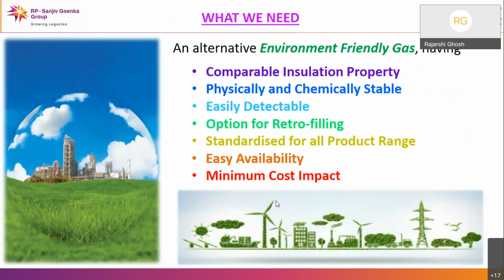So what we need is an alternative environment-friendly gas having insulation properties comparable with SF6, physically and chemically stable, and easily detectable so that leakages can be detected easily. There should be an option for retrofilling because we have a huge number of old GIS. Presently in CSE alone we have more than 900 GIS bays at 220 kV, 132 kV and 33 kV levels. It should be standardized for the whole product range, that means the gas should be the same for the different voltage levels as well as for different manufacturers, with easy availability and minimum cost impact. So all these things need to be addressed.